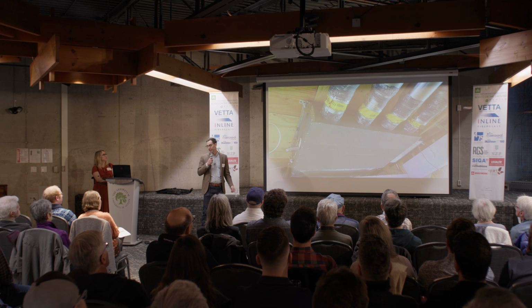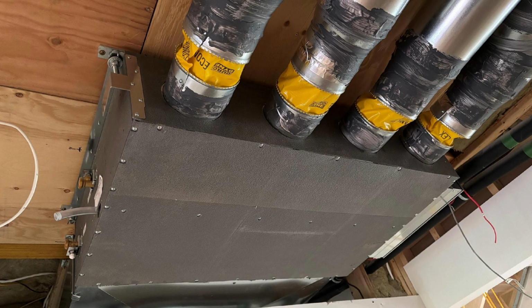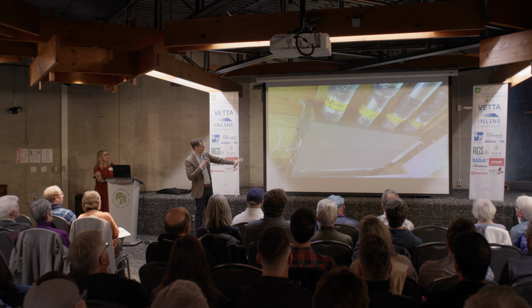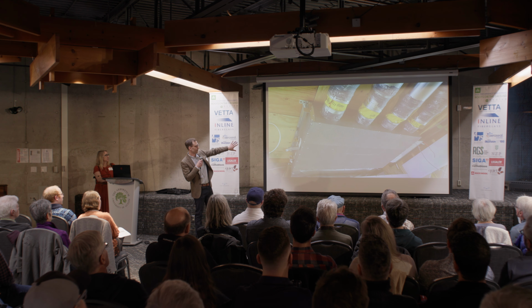This is the 4-duct again with the flex collars installed now. They're 6-inch, we step up to 7-inch after the flex collar to try to lower the velocity moving out through the house and keep the duct velocity low. This is before the hydronic connections had been done or the control wiring.